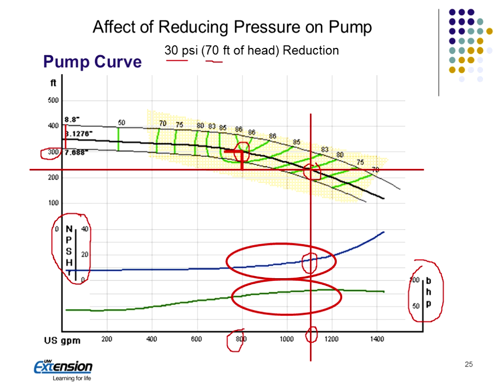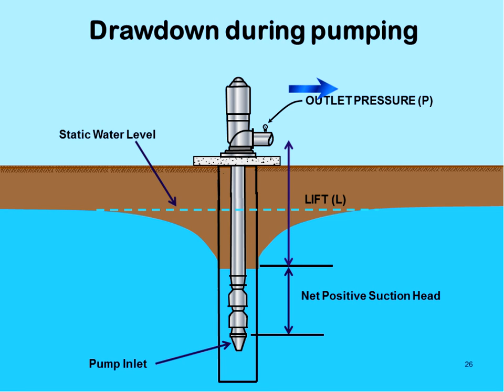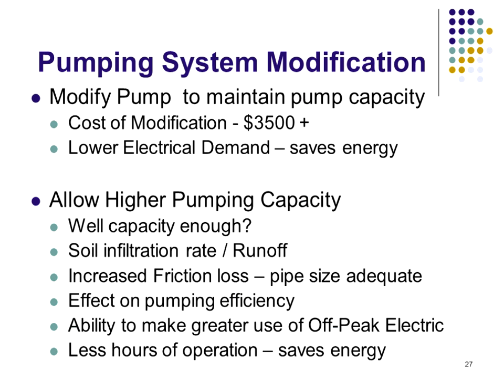The green line here is brake horsepower. So we've gone here from this would be the 75 line, so about 70 horsepower to maybe about 78 horsepower up here. So it just shows that it does increase the horsepower slightly. The way we save money if we do this is because we've got to run less time because we're applying more water. So this graphic tries to show you. So here's the water level when the pump is not operating, and when we start operating the pump, we get this cone of depression, it's what it's called, where the water level will decrease. So we want to make sure that we have enough water above the inlet here, which is the net positive suction head, to prevent cavitation. So that's what we're trying to show there.